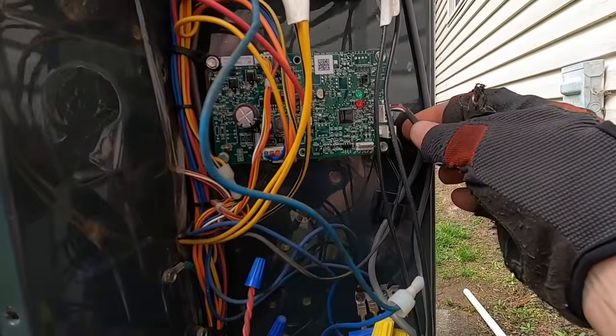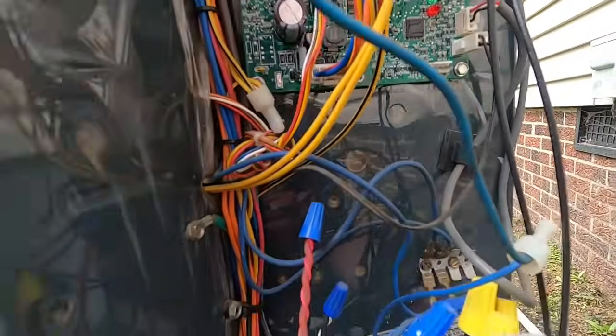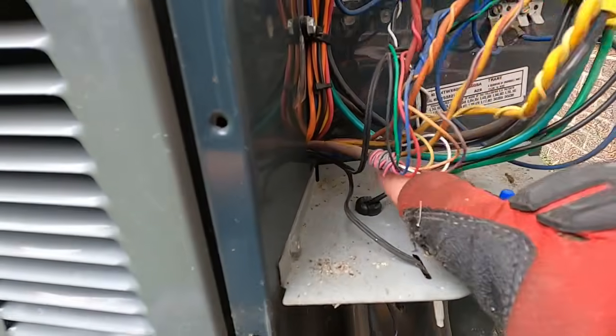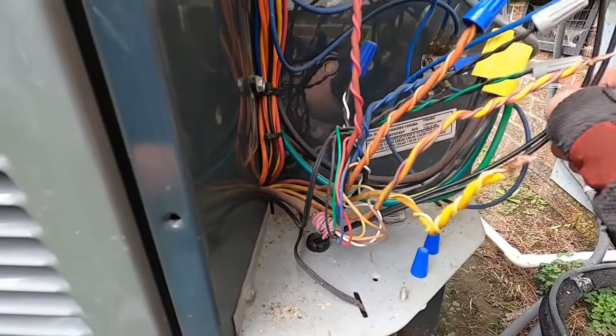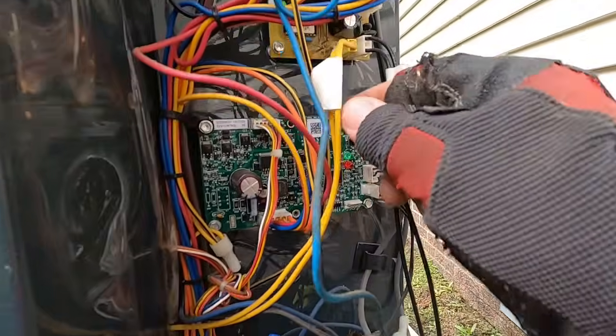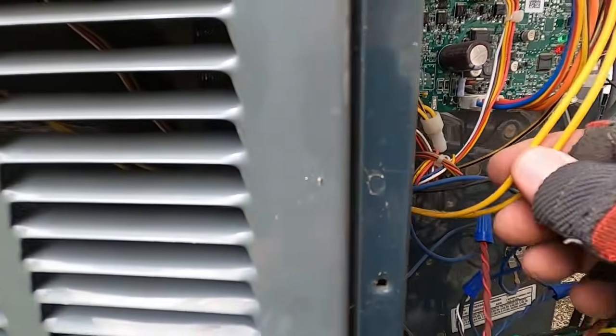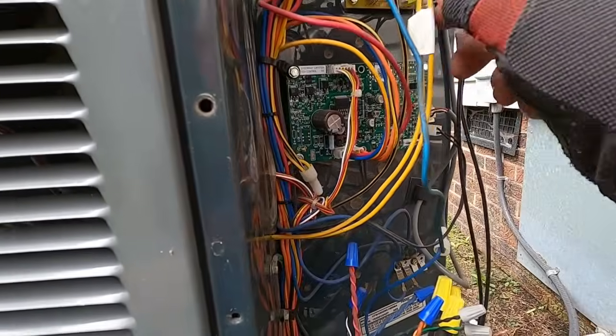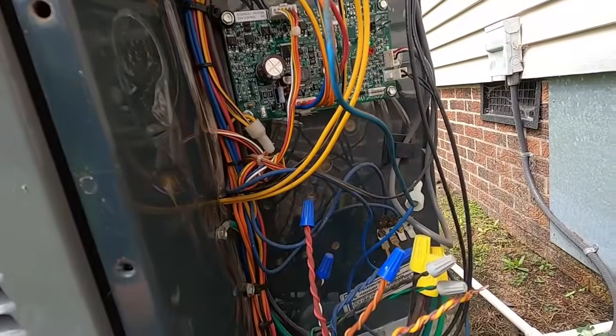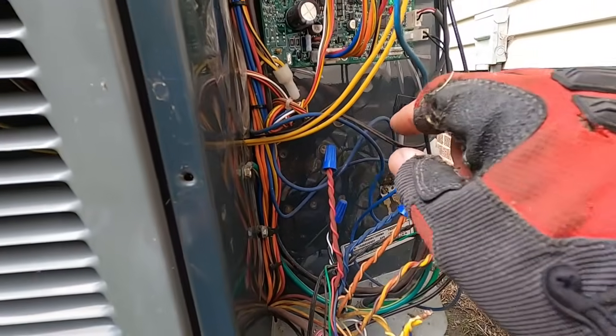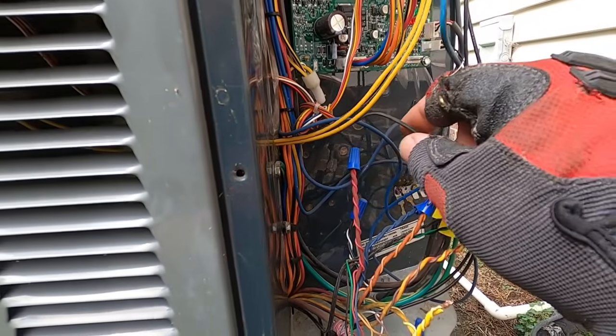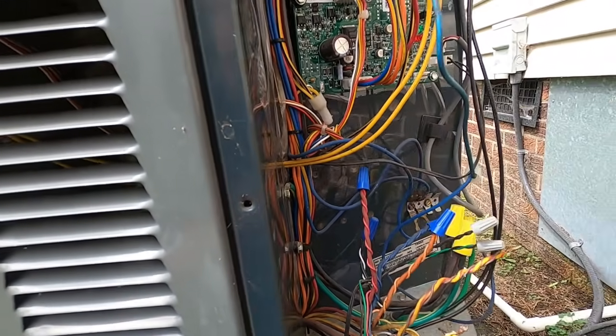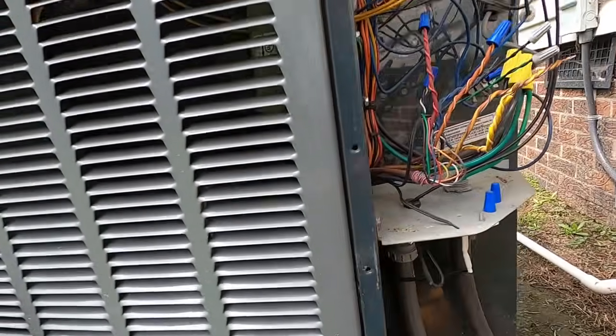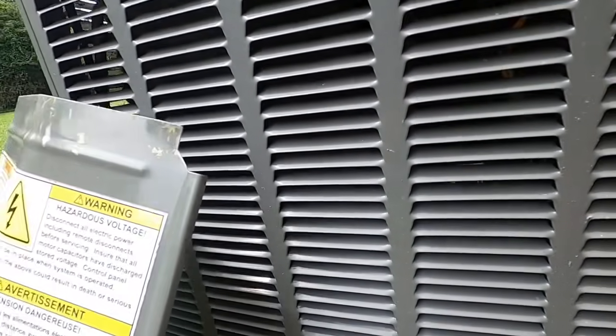And your suction pressure transducer is plugged here. Your outdoor ambient temperature sensor goes to your defrost board. Your coil sensor goes to your defrost board. You also have your temperature sensor here that I was telling you about. Let's pull the side panel off real quick.